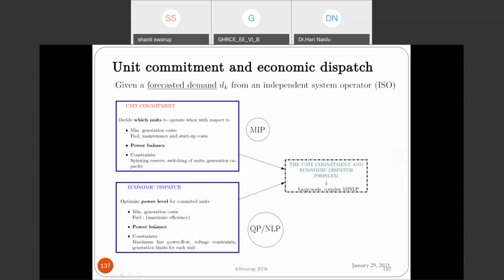We have power balance, we have constraints. In economic dispatch you use quadratic programming and nonlinear programming, whereas in unit commitment you use mixed integer programming because the units can be on and off. Here we have spinning reserve, generation capacity - many other constraints come into unit commitment. Whereas economic dispatch, you have only power generation minimum limits. You can even include voltage limits, but the minimum thing is minimum and maximum generation limits.